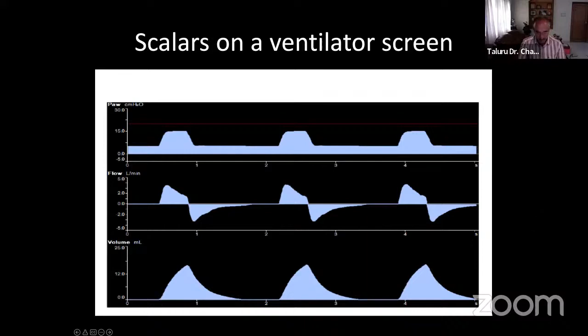This is a decelerating flow. This is not a square flow. This is the flow versus time scalar because there is a representation below the baseline. See here, again, it starts from here. It will go inspiration, then it will come back to expiration. If it doesn't come back, there is always a pathology. Here also, it will go like this, then expiration, it has to come back. You have to remember, see, there is a representation below the baseline.